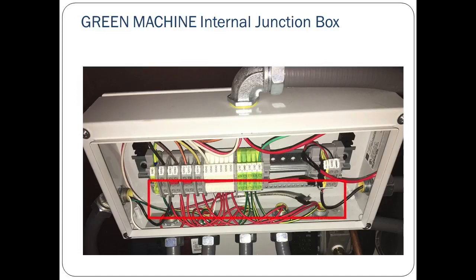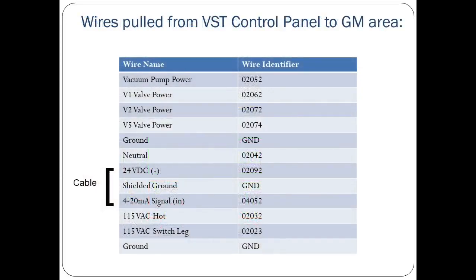All connections within the red box are on the bottom of the terminal blocks and come pre-wired from VST's production facility. The electrical contractor is only responsible for terminating wires to the top side of each terminal, so do not do anything with the wires at the bottom of the terminal block. This table shows each of the wires and its corresponding identifier.